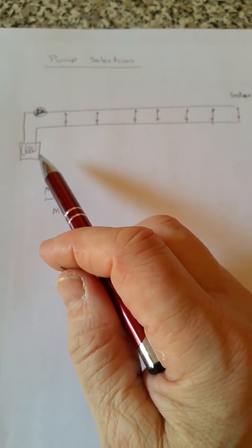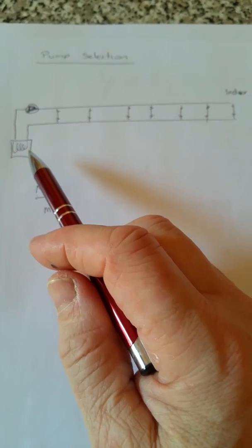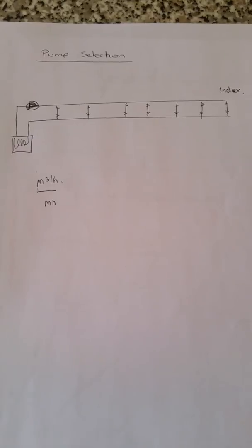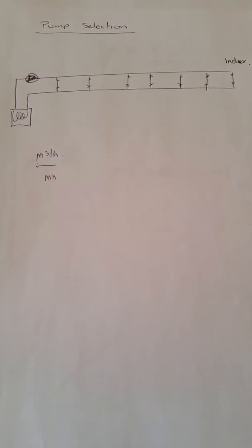And this is going to be very hard to do because it needs to be done under full load circumstances, and that means full output of the boiler. And it's very hard to get full output of the boiler and full output of the radiators to run while you're commissioning, unless you've got the design criteria delta T between the inside temperature of the room and the outside temperature of the property.